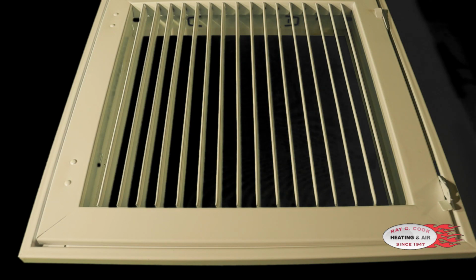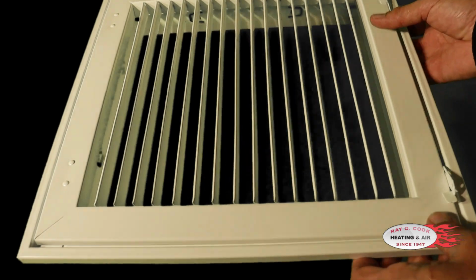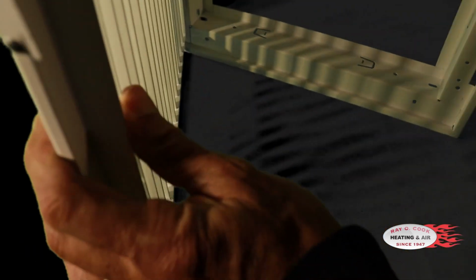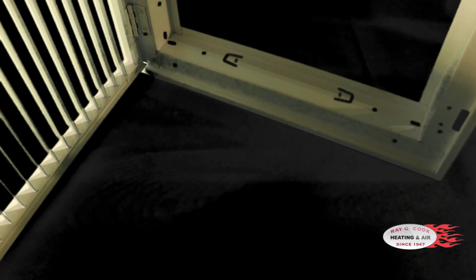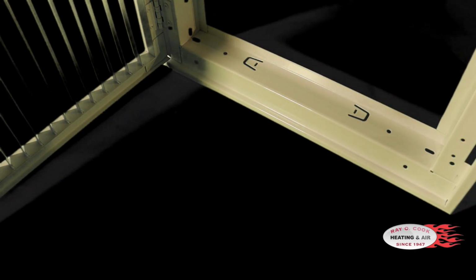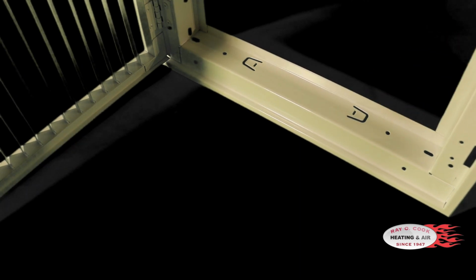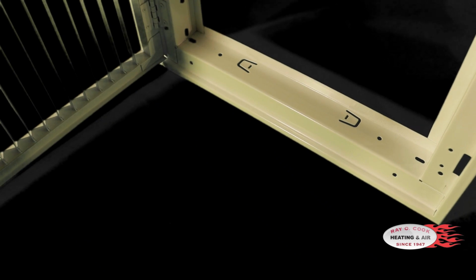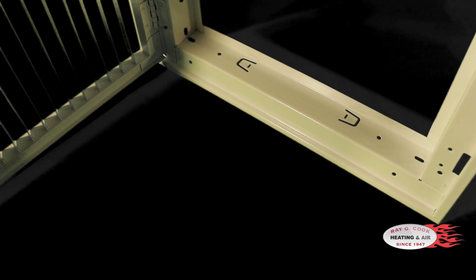And what will happen with regards to air quality and performance of the system. So this is just a small 12 by 12 filter grill so that we can handle it easy for the video. But when we open this up and we open the grill here, what we see is a track. So when we put a track in this filter grill, that's to hold a 1-inch filter. So when we put the filter in that's too restrictive, what we don't accommodate for and what we don't talk a lot about, which is a major deal, is what's called bypass.